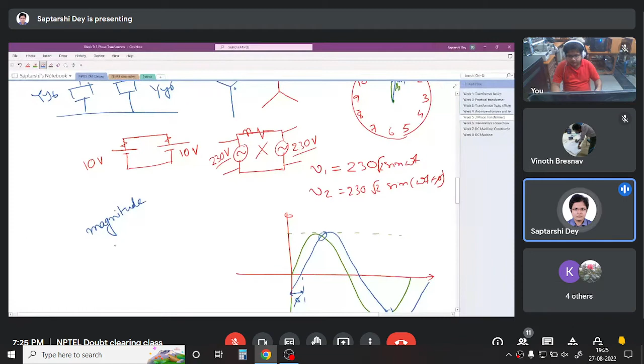So there is a large current flowing. So when you are paralleling transformers, you have to make sure that not only the magnitude of voltage is same, but also the phase should be same. Then only you can connect two transformers in parallel. That is why these phase groupings are important. If you are using one single transformer, it doesn't matter whether you are connecting it in YY0 or YY6. But if you are connecting in parallel, it matters.